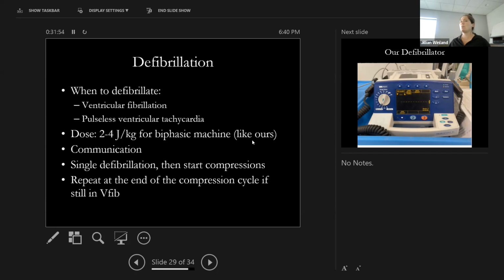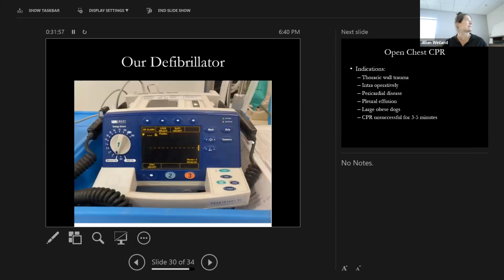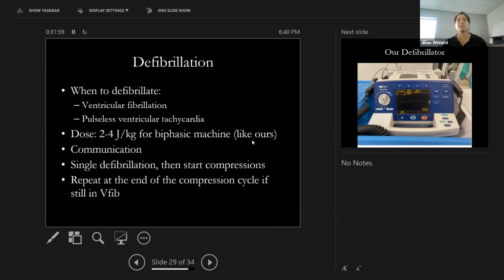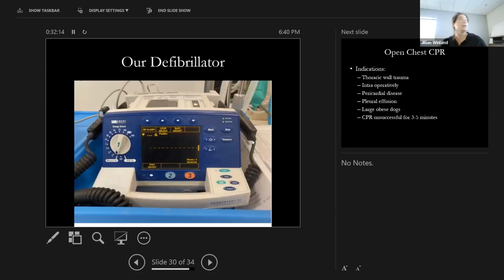And so the defibrillator needs to be set, that's this thing. It needs to be set to 2 to 4 joules per kg for a biphasic machine, which is this one. And so usually you start low. So in a 10 kg dog, you'd start at 20 joules, which you can set on the little knob there on the left. You see it goes 2, 3, 5, 7, 10, and then 20. So in a 10 kg dog, you would turn that dial all the way up to 20.